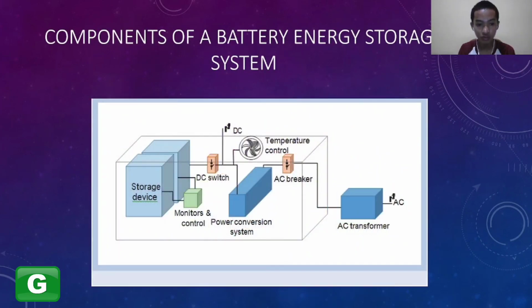Components of a battery energy storage system: it is shown here what composes one - the storage device with monitors and control, a DC switch, temperature control which is important to regulate the temperature of the battery system, a power conversion system, an AC breaker, and an AC transformer. Because battery energy storage systems store electricity in the form of DC or direct current, for it to be used we need to convert it into AC. That's why there is a power conversion system.